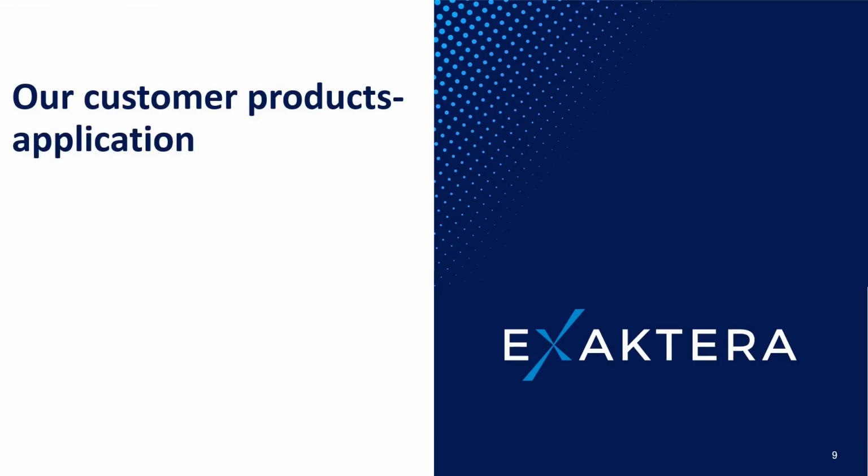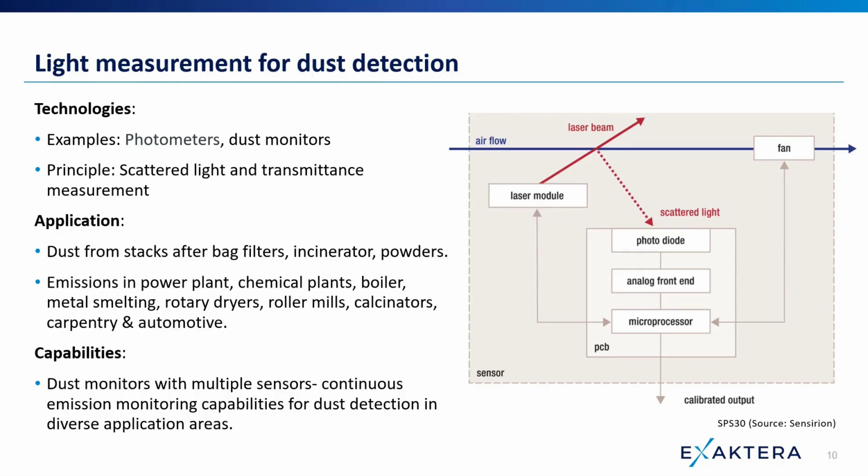Okay, I want to move on now to take a look at a few customer applications supported by Exaktera with our laser technology. We have a number of customer applications in dust detection, either for monitoring the effectiveness of bag filters by measuring the dust in a post-filter stack, or for monitoring soot release from incinerators or powders escaping from powder production facilities like cement works, mills, industrial calcinators, or metal smelting works.